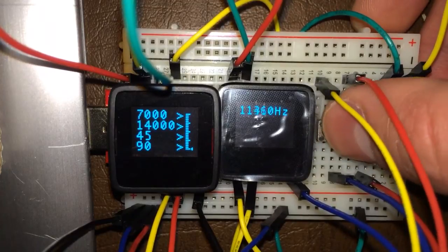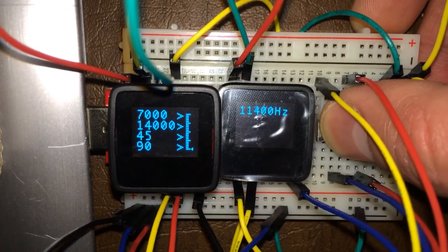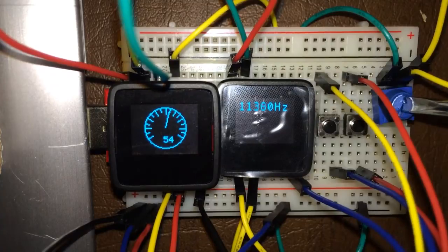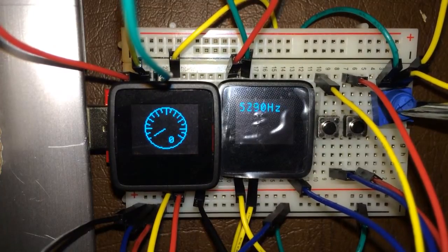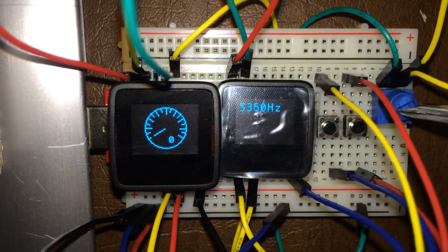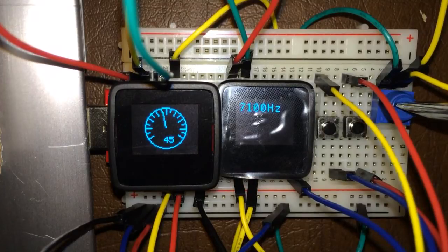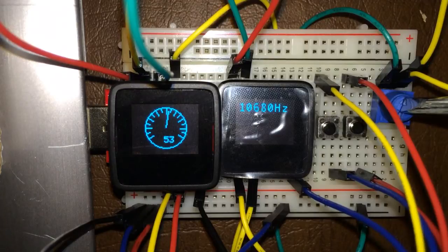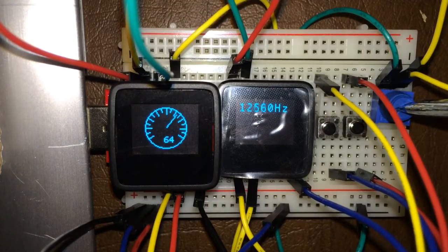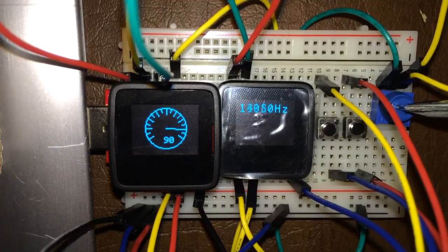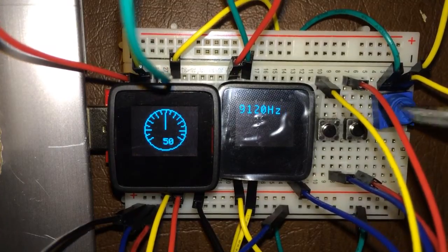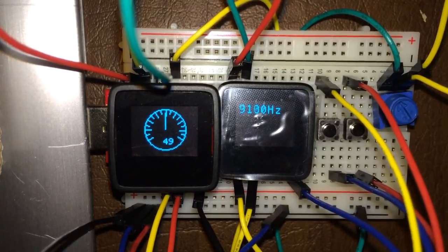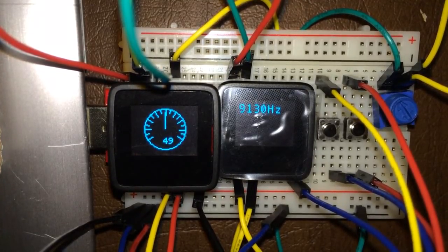Now we'll show how the bend factor works — we'll set it all the way down. We'll turn this off and then ramp up slowly so you can see. Now it's active and the frequency is still going up but the pump's not really changing its duty cycle — but pretty soon it's going to come on really hard and ramp up very quickly to whatever your maximum is.